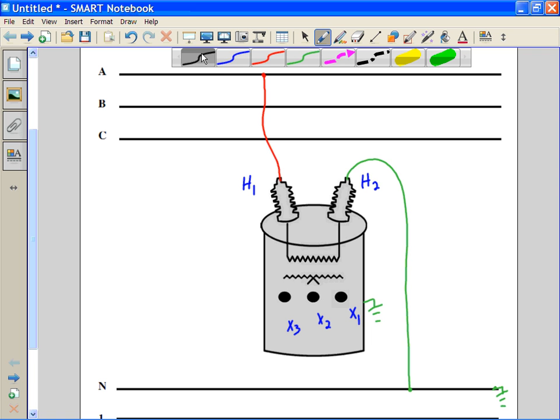Now we need to connect the internal secondary coils of this transformer so that we can make full use of the transformer at 120 volts. In this case, we want to parallel the coils together. In other words, we're going to connect the left side of each coil together and the right side of each coil together, and then we'll bring the left side down to X2, and the right side will come down to X1. X3 is just an unused bushing in this particular case.